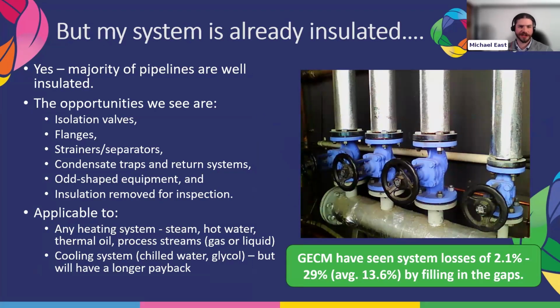So your thermal system's already got insulation - yes, most pipelines are well insulated. There are some where it's been removed for inspections, but what I'm talking about, as I said, is filling the gaps. The areas we've seen opportunities are your control valves, flanges, strainers, separators. Where you're using the steam, you might have a cooking appliance or a direct injection process with an odd-shaped piece of processing equipment, and the shell of that is radiating the heat from the steam inside.